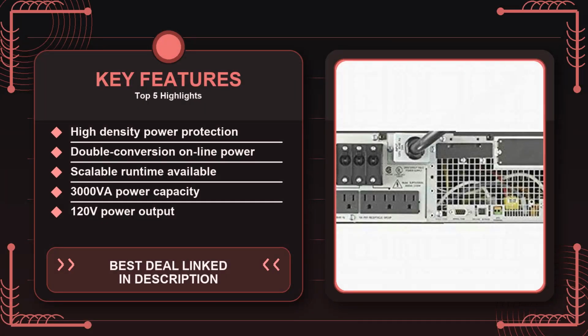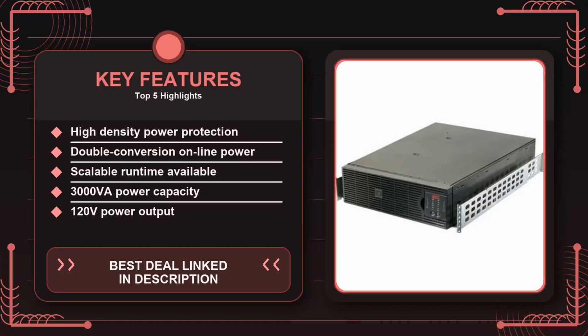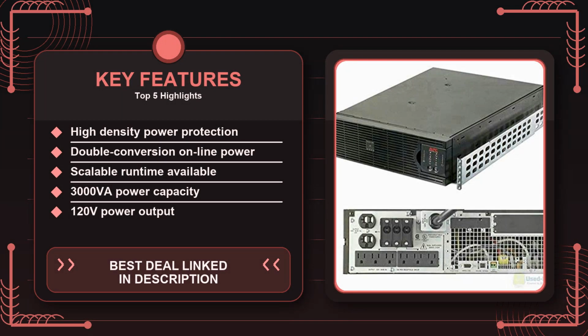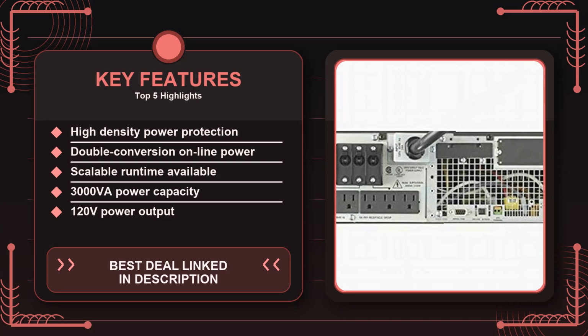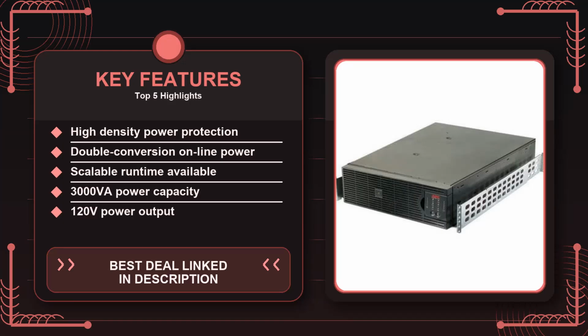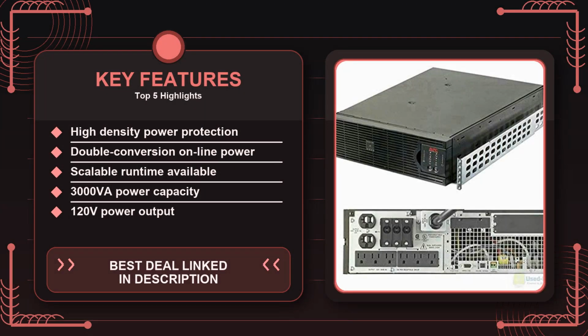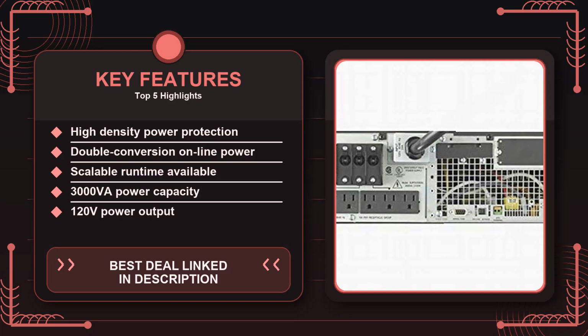If you're an IT administrator who wants a UPS that can sit on a standard 19-inch rack without taking too much vertical space, the 3U height is actually a benefit. You'll find that most rack shelves accommodate it without sacrificing an entire shelf for a bulky power unit. That's a win if you're trying to keep the footprint tight and preserve room for future hardware. On the other hand, if you have a full-size data center with redundant power feeds and you're already using larger, modular UPS cabinets, this unit may feel a bit small. You'd be better off looking at APC's modular lines that can scale to megawatt capacities.